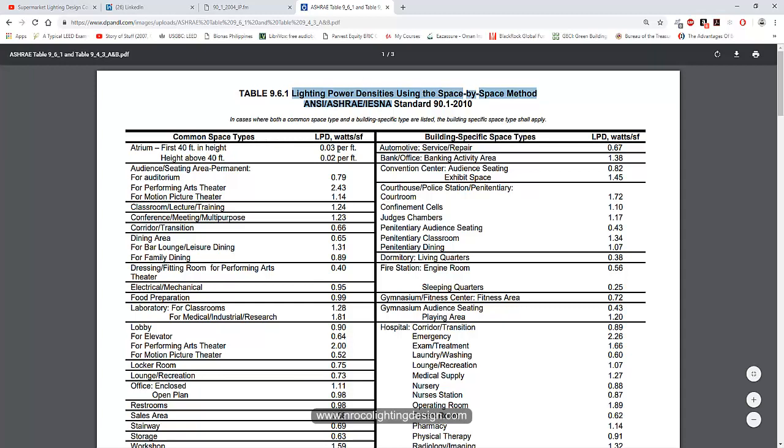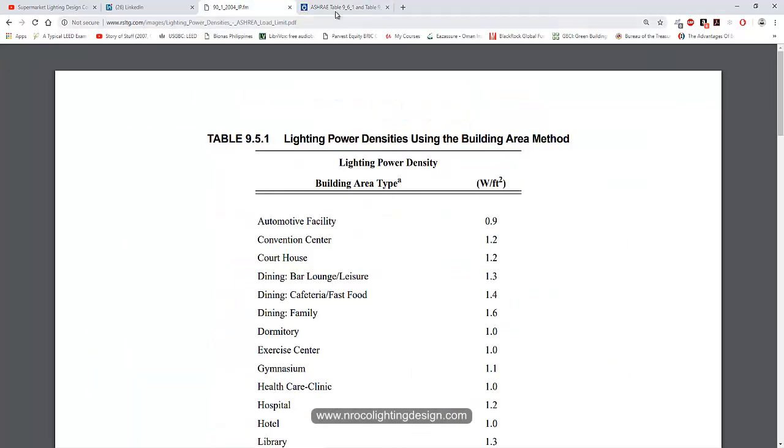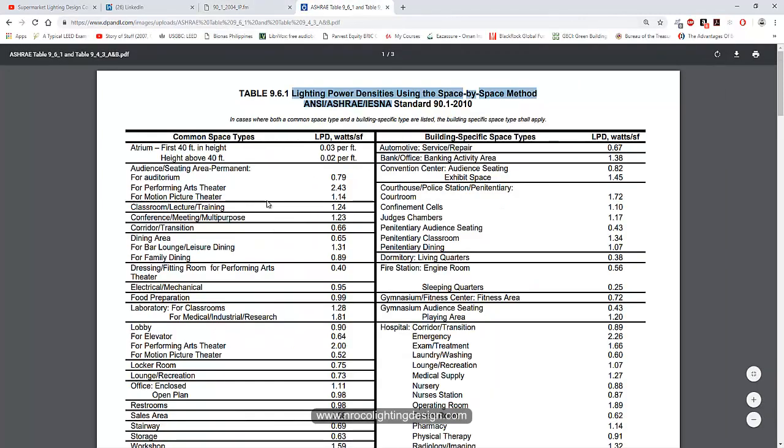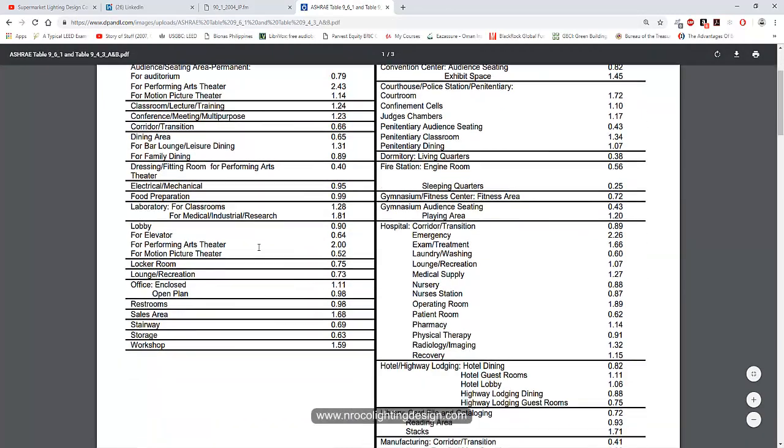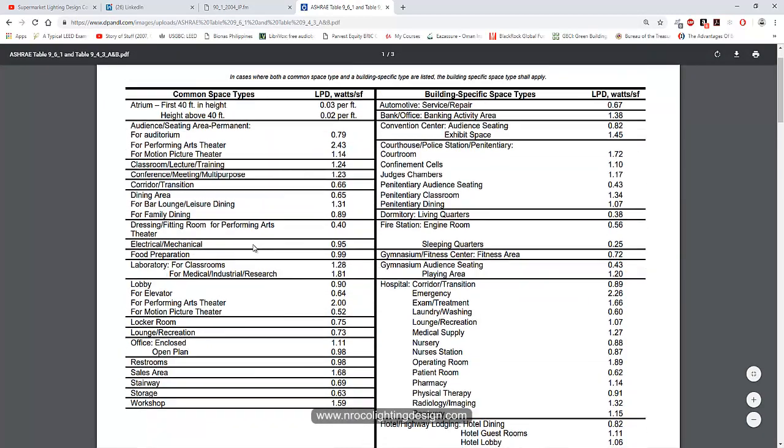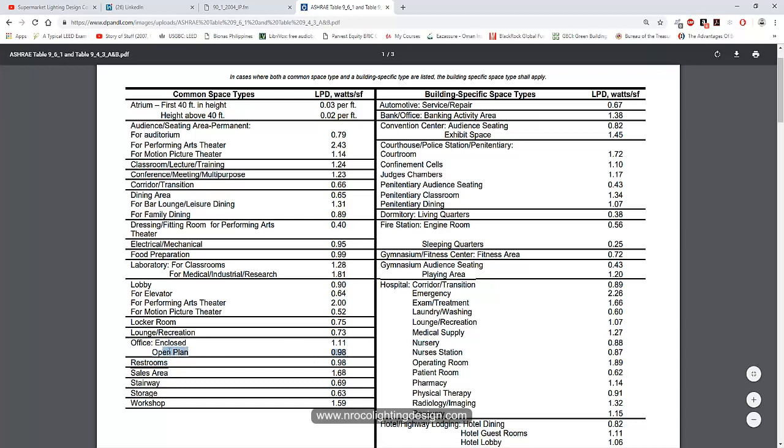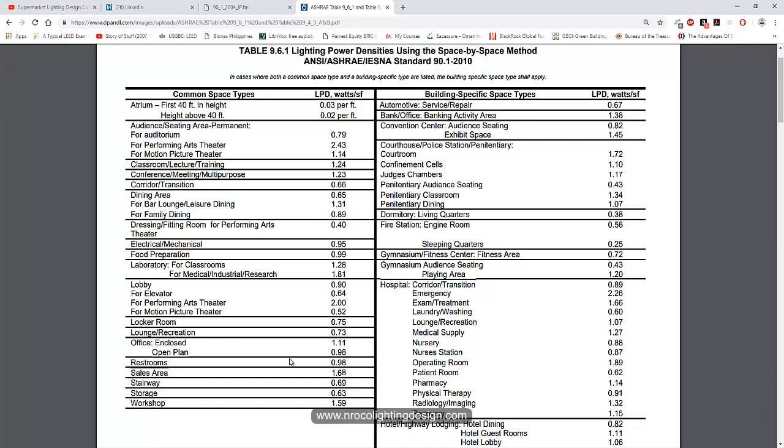For example, you can see here a lobby is 0.9, restroom is 0.98. For an office, open plan is 0.98 and enclosed is 1.1. If you want to convert it to per square meter, you can search online.